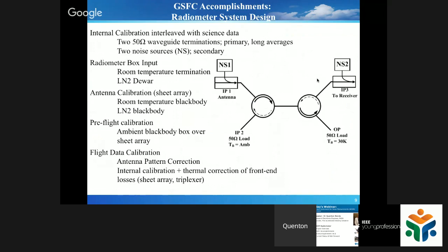So the concept here is, if you think of a straight line, for radiometers we detect a brightness temperature. That brightness temperature is a function of the output voltage from our instrument. If I have a cold target that's physically cooled, that target will provide a voltage. A hot target, which is my ambient target, is hot because it's warmer than snow, and that calibration reference provides a voltage. We're measuring snow, which is in between those two calibration loads. That's how we translate voltage to brightness temperature. Conceptually, we know the brightness temperature of our physical standards, and when we take measurements, we use the equation of the straight line to calibrate and figure out the brightness temperature of the snow that we are measuring.